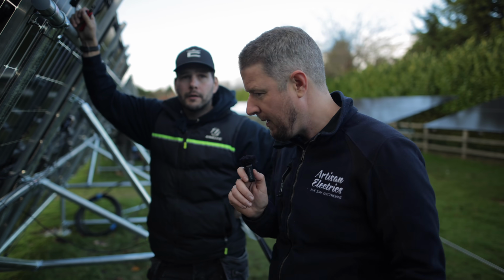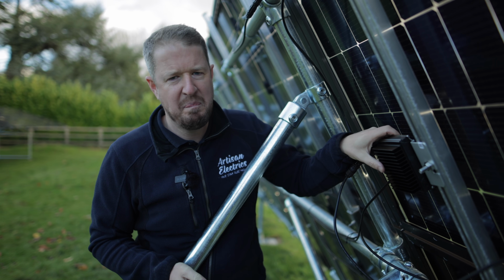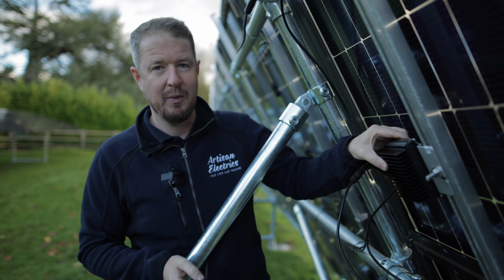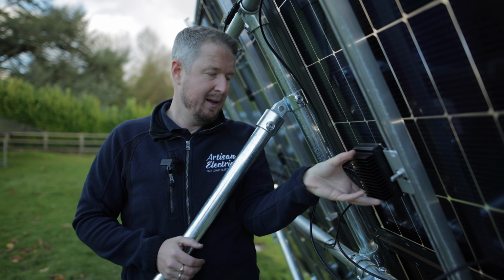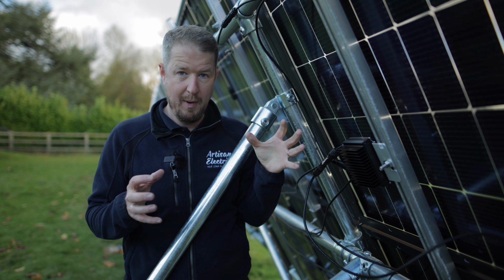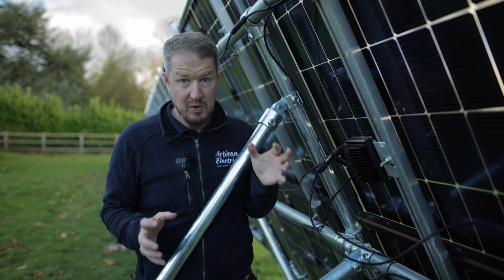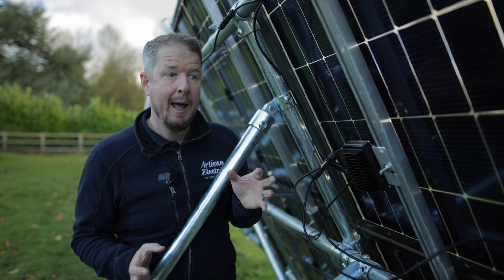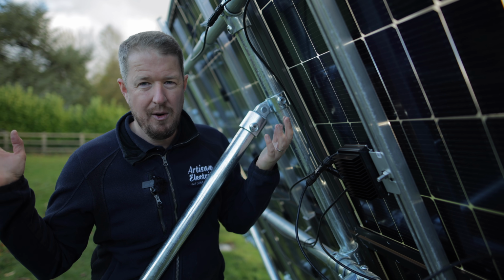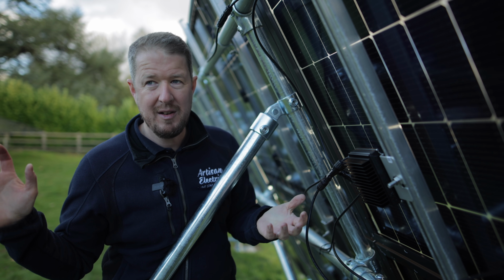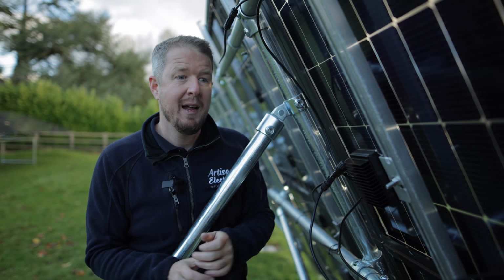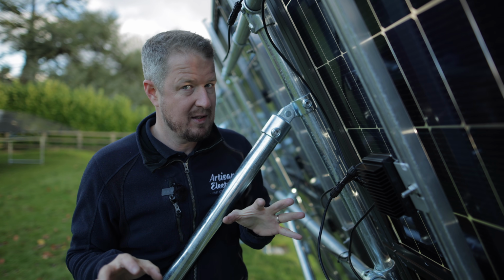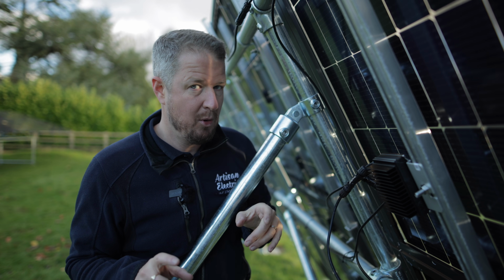So you might wonder, what are these strange boxes we call optimizers that we're installing? They're exactly what they say on the tin: they optimize the performance of the system because we're using a SolarEdge system here. Now you might wonder, why use SolarEdge instead of a normal string inverter, which they use for a lot of ground mount systems? There are a number of reasons why we decided to do SolarEdge on this one, I'll tell you more later.